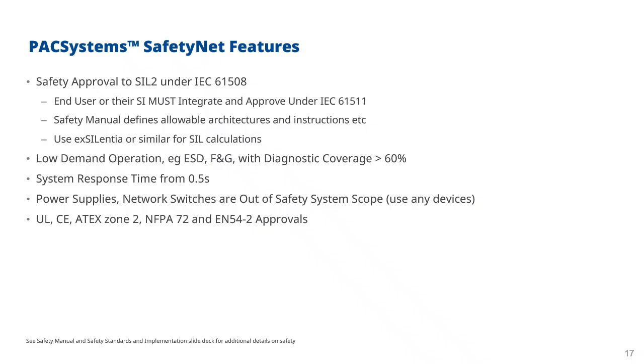Now, as well as the safety certificate and approval to SIL 2, we do have other approvals as well. So there's UL and CE marking. Everything is approved to ATEX Zone 2. We also have NFPA certification. NFPA 72 is for fire and gas in the US. EN 54-2 is the European equivalent for fire and gas systems. And there's also some other NFPA approvals as well for burner management systems.